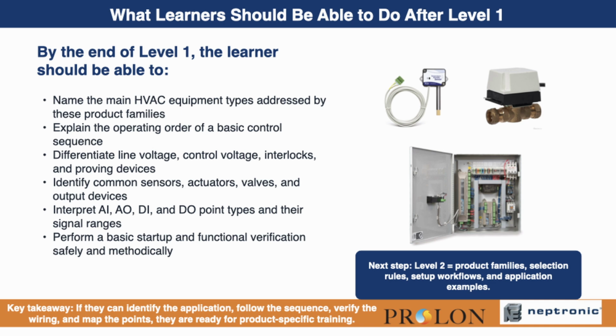By the end of Level 1, the learner should be able to identify the main HVAC applications addressed by these product families, explain the basic operating order of a control sequence, distinguish power wiring from control wiring, recognize common field devices, understand analog and digital I/O, and perform a structured basic startup verification. This does not mean they are finished learning. It means they now have the foundation required for Level 2, where training becomes more product-specific. Once this base is in place, it becomes much easier to learn controller families, set up tools, selection rules, and advanced commissioning workflows. Level 1 gives them the operating framework. Level 2 will teach them how each product family is applied within that framework.